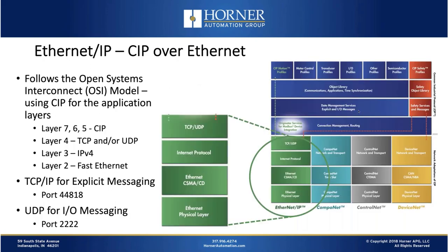We've talked about Ethernet IP from the standpoint of the general market, and we've talked about CIP, the underlying object-oriented data and messaging structure. Let's complete the picture by examining the marriage of CIP with Ethernet. In the seven-layer open systems model, CIP resides at the application layers 5, 6, and 7. Layer 4 is where the transports TCP and UDP come in. Layer 3 is the internet protocol layer, and Ethernet IP uses IPv4 addressing. Layers 1 and 2 are the Ethernet physical layers.